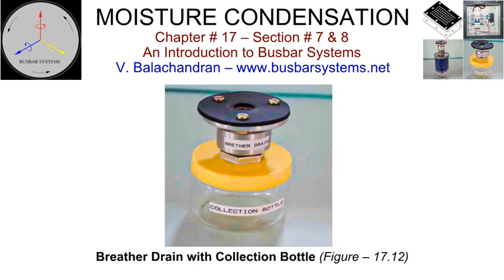Breather drain with collection bottle. Drain cum filters are installed on the enclosure of the air-insulated busbar system at the lowest location to drain out the condensed water. The selection of the assembly is critical as it should be ensured that the degree of protection of the enclosed busbar system is not compromised with its installation.